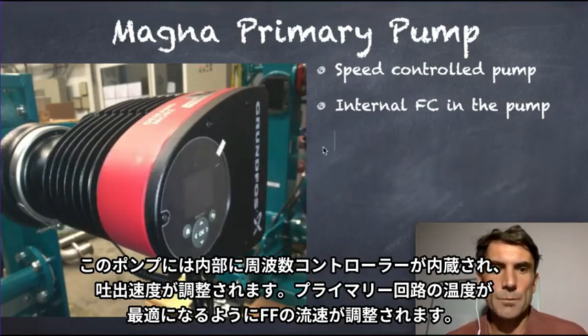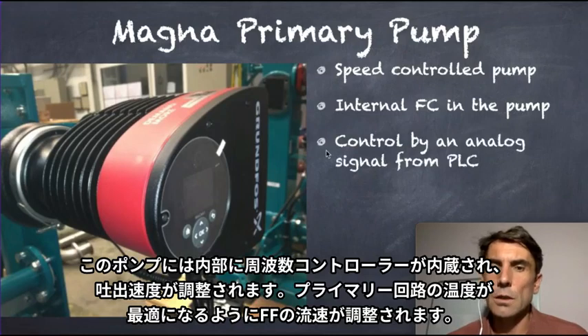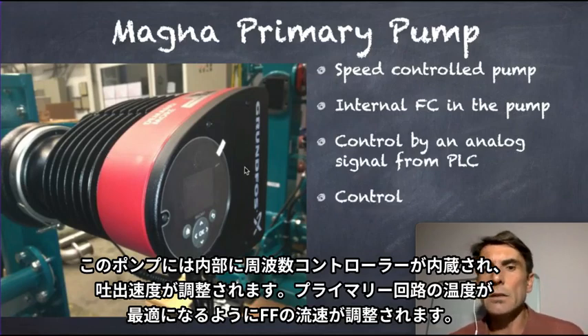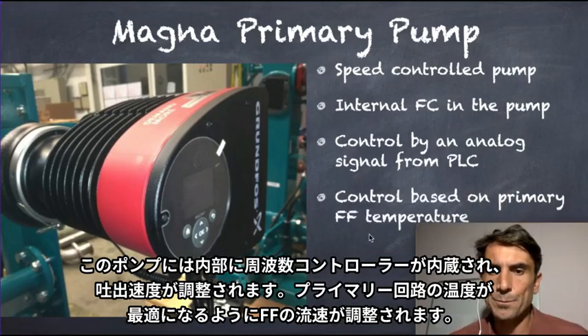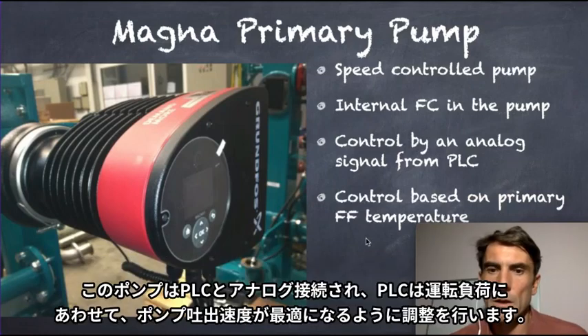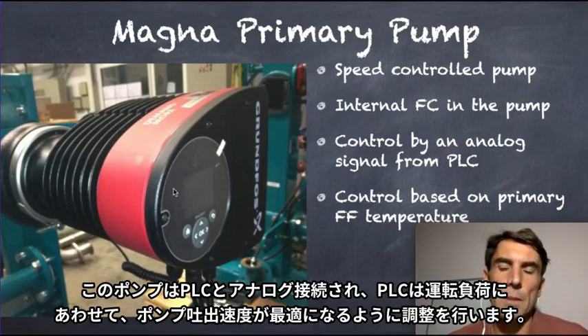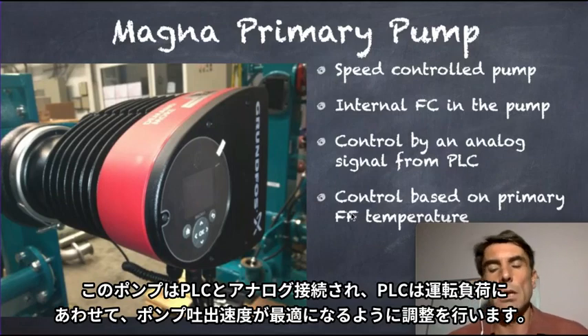Internal frequency converter, and can control the speed of the pump, so that we get the ideal forward flow temperature for our primary system. And the pump is connected via an analog signal to the PLC. So the PLC controls the speed of the pump via analog signal to get the ideal forward flow temperature on different loads of the CHP and keep the temperature stable for a nice and highly efficient heat supply to the plant or to the client.